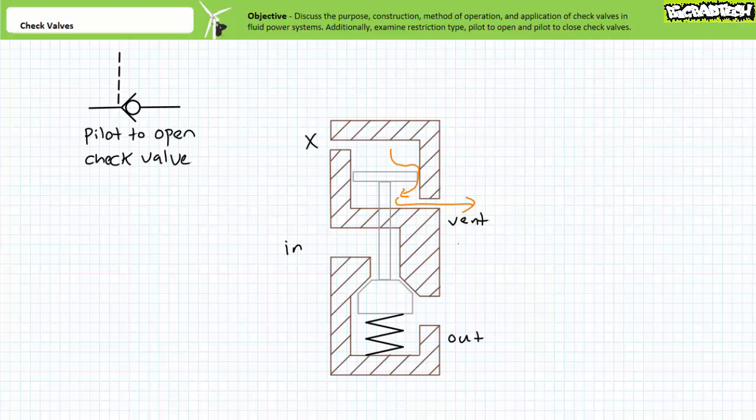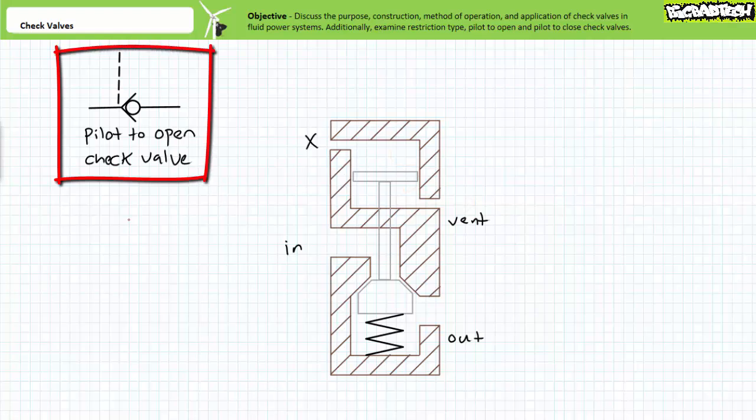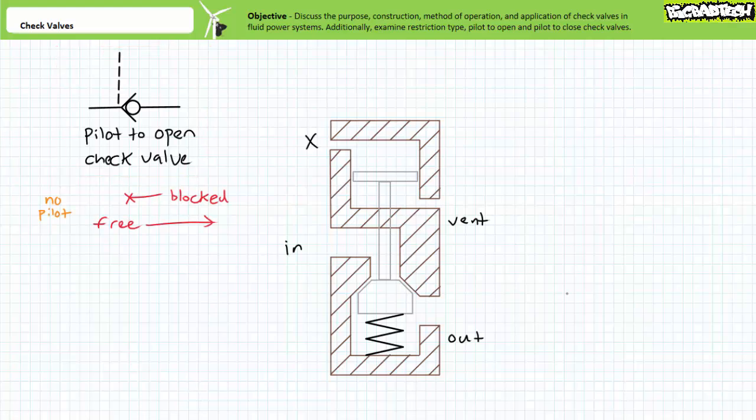Note the comparatively large area of the pilot piston allows it to hold open the ordinarily blocked direction of the check valve even with comparatively smaller pilot pressure. The schematic symbol for a pilot to open check valve is just like a regular check valve, only this time it includes a dashed pilot line on the seat side that pushes open the ball. Again, a pilot to open check valve acts just like a regular check valve in the absence of a pilot signal.